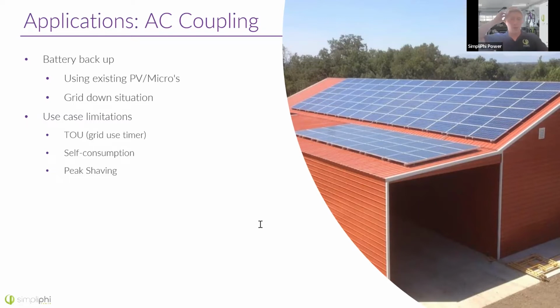Yes, so this can be done without frequency shifting. You need to make sure that, and I would check this with the lead acid batteries before you put on the lithium batteries, when the battery-based inverter senses the batteries are full, check that it actually turns those microinverters off, or excuse me, that string inverter off quickly and effectively. Make sure that battery voltage is not rising above what it should be and what you've programmed into that system in the Mate 3. So if that system is actually working well and turning off and charging the batteries as you've programmed it, sure, you can add those in, and you don't actually necessarily need frequency shifting. It's going to make things more seamless, but I understand not having it. It's totally going to be okay without that.